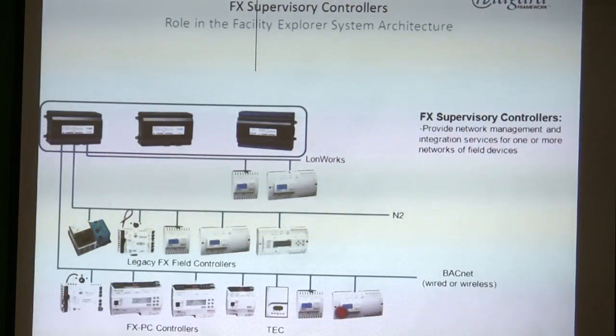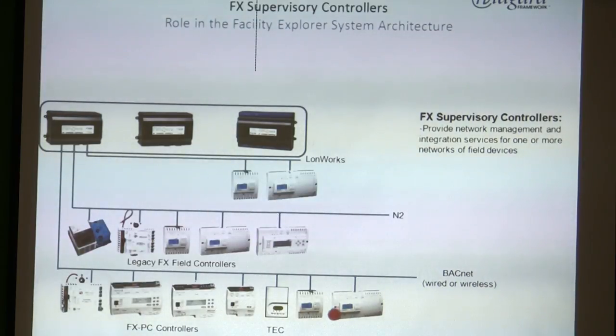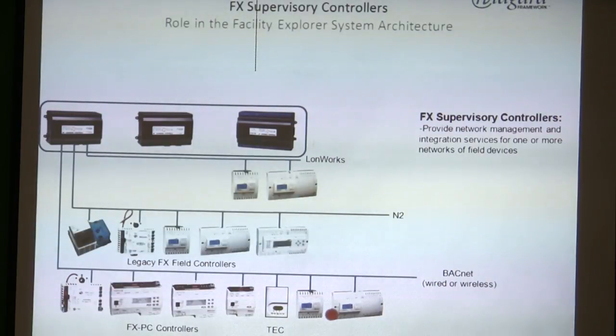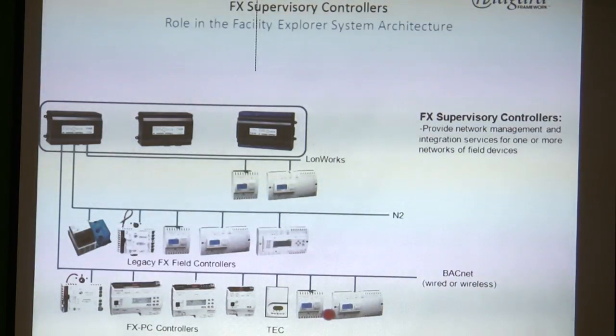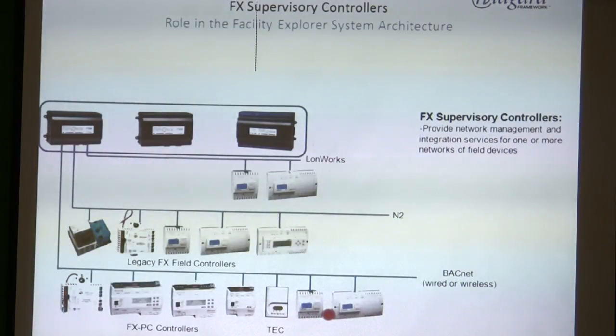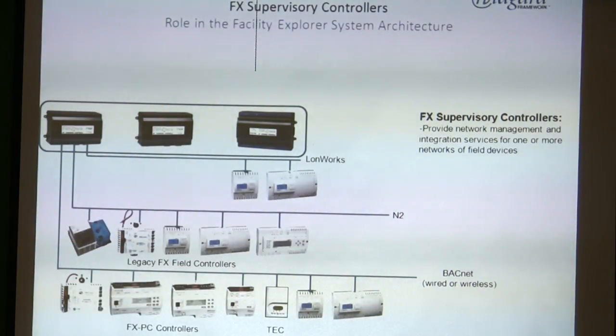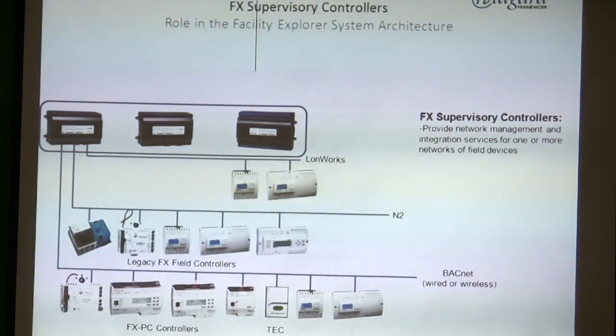This goes into what we were discussing — you can have the newest stuff sitting on the same bus as the old stuff. If you're going to retrofit a building, you can leave what's working in place and add the new stuff as you get money, replace by floor, or as controllers break. One old controller goes bad, you replace it with a new one on the same bus and you're good to go — as long as it's the same protocol.